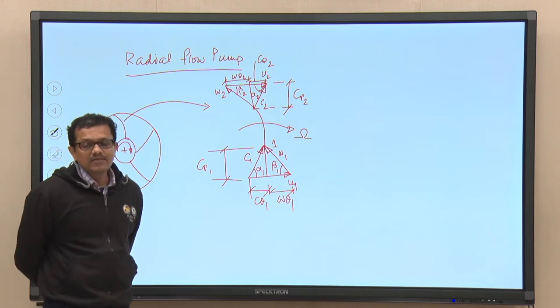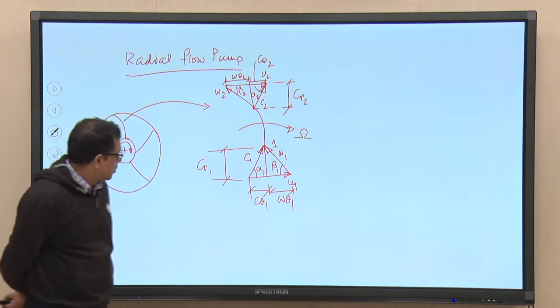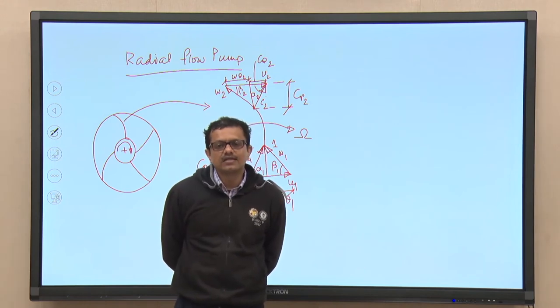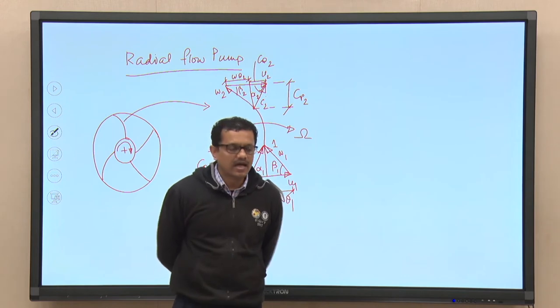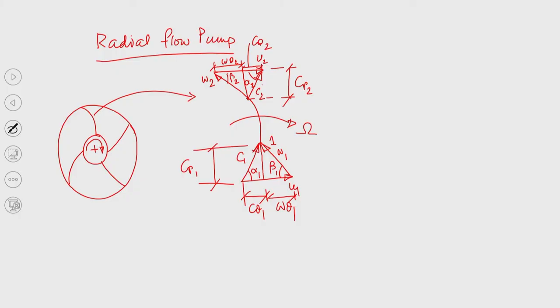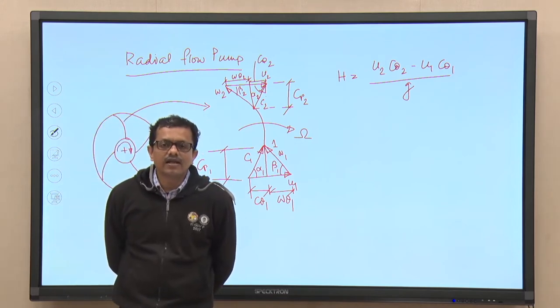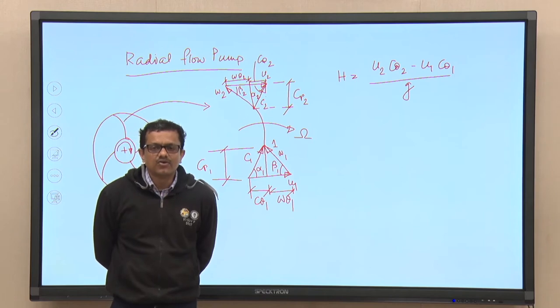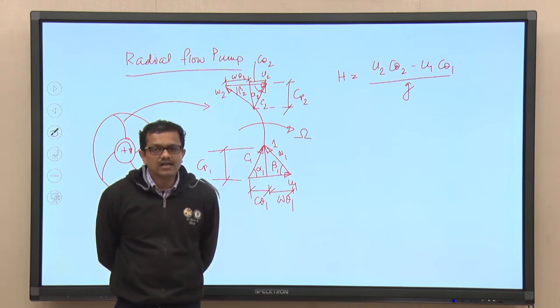The impeller is rotating at angular speed omega. The most important expression for the pump is the head developed, given by Euler's equation: H = (u2·c_theta2 − u1·c_theta1) / g. This expression gives the ideal head — frictional and other losses are not accounted for.